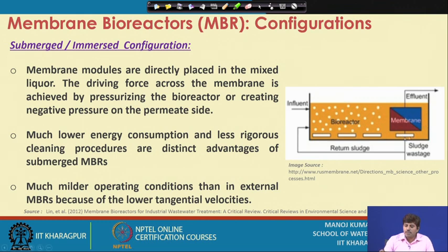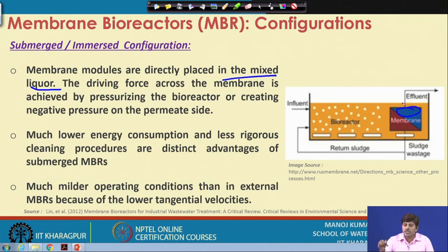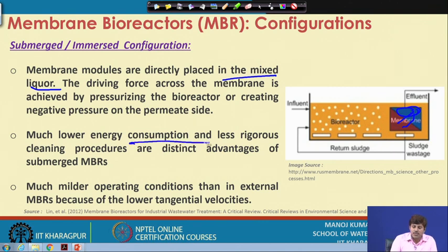To reduce energy consumption, the submerged or immersed configuration was developed, where membrane modules are placed directly in the mixed liquor inside the bioreactor. The driving force across the membrane is achieved by creating a vacuum on one side, which sucks water through the membrane — the permeate exits and the retentate remains within the reactor. This eliminates the need for a separate channel or system, resulting in lower energy consumption and less rigorous cleaning processes.